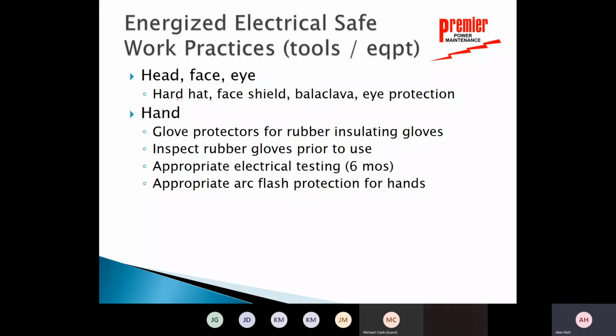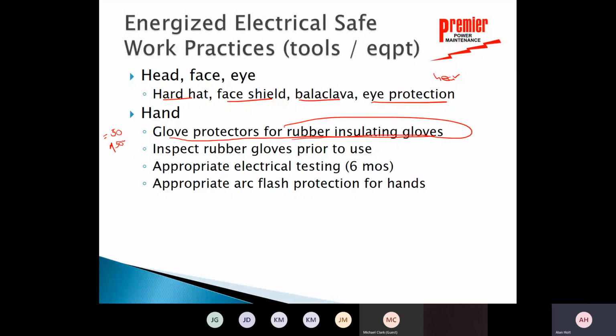Basically for us, if it's over 1.2 calories per square centimeter, or 1.2 calories and above, we need a hard hat, face shield, balaclava, and eye protection. We also have to have hearing protection, so we have to have our ear inserts in. Our hands have to be protected. We have glove protectors for our rubber insulating gloves. Basically, any time that we are at 50 volts or greater, we have to have rubber gloves on. That's even for using voltage devices like our Fluke. That's even if you have an insulated screwdriver. The voltage gloves are required with the glove protectors.